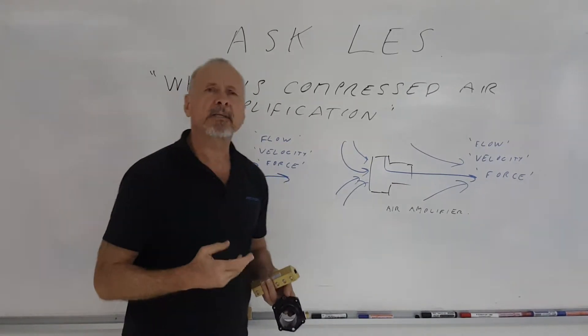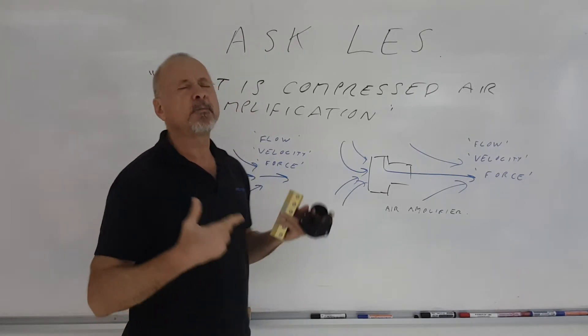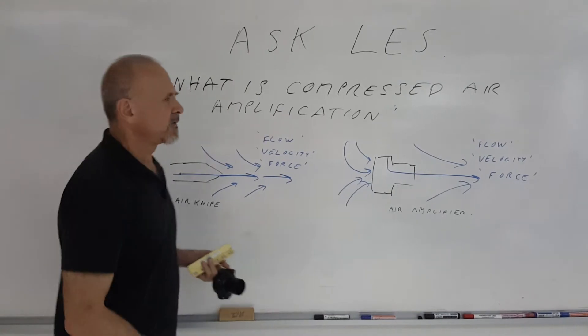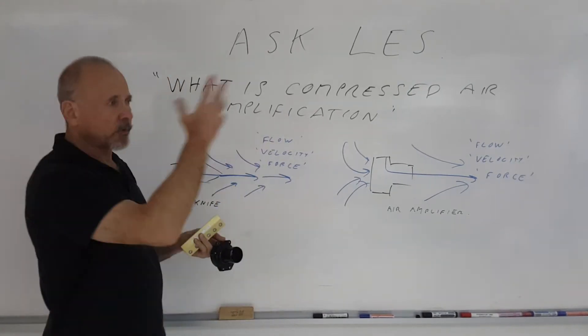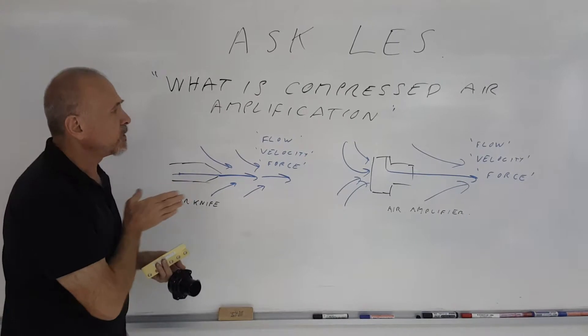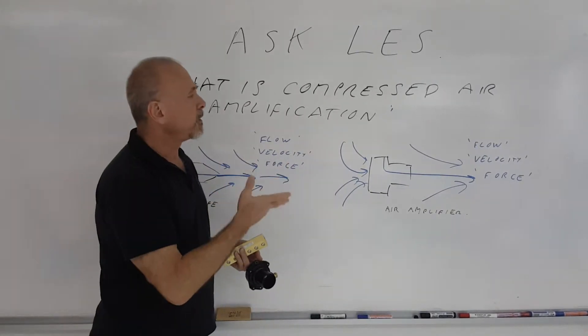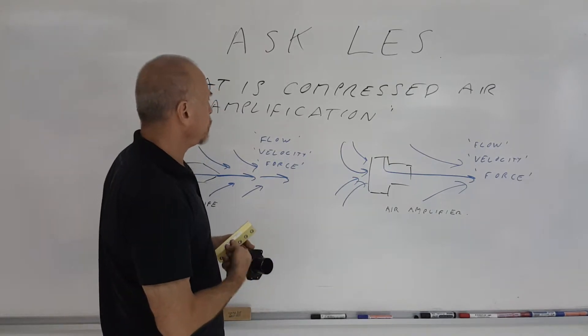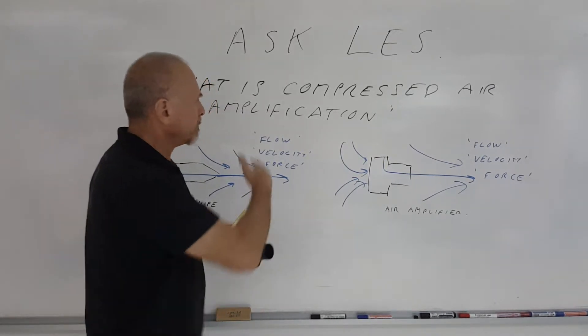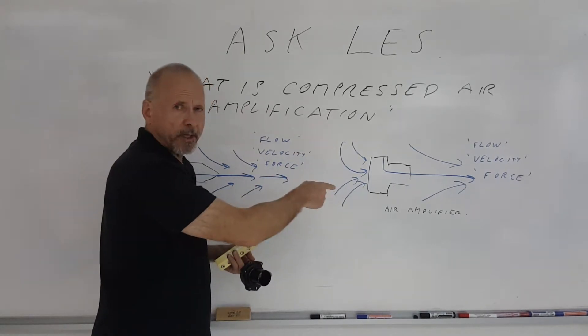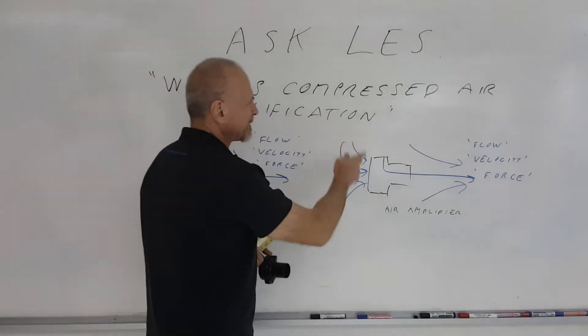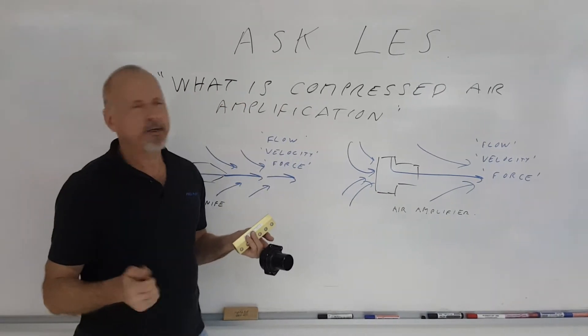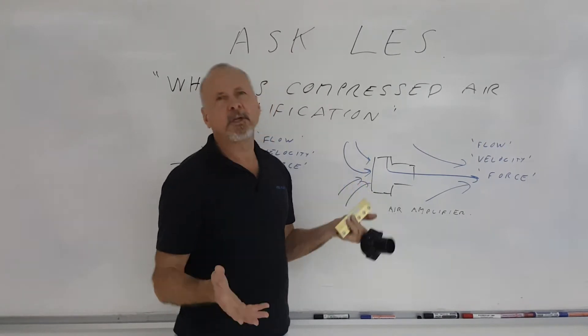That amplification is also an approximation. It's going to be different depending on the condition of the particular day. For example, if you have a very hot day and the surrounding air is less dense, your air amplification is actually going to be much higher than it would be on a day which is a lot colder. Secondly, if you have a different pressure of the compressor going in, it actually amplifies better when the compressed air is at a lower pressure. However, that doesn't really mean anything.